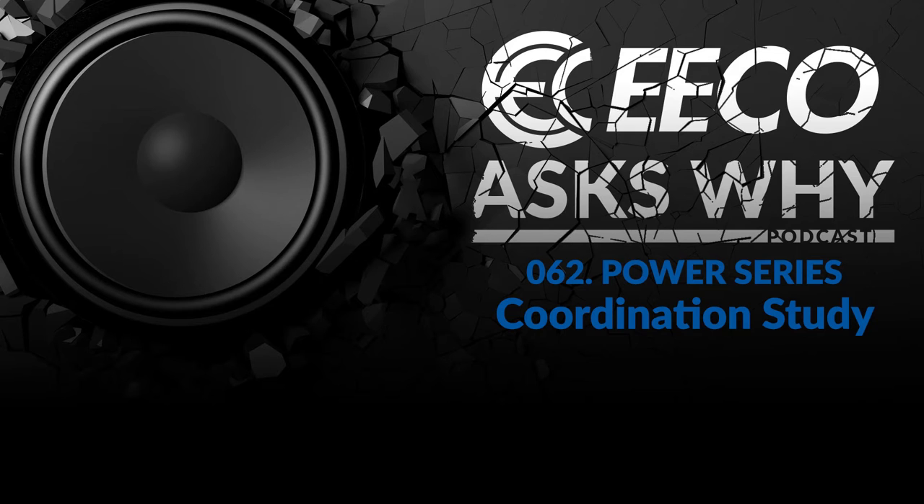We love to get to the why, so why should they consider a coordination study? A coordination study is important because unless protective devices are properly set, your system may not run. Factory settings are usually set to minimum, and a lot of times those are too low for motors to run. So they need to really be looked at prior to energizing equipment. The second reason is that your protective device may not be set to trip fast enough during a fault. Both of those are important — to run your equipment under normal conditions and to clear a fault appropriately.